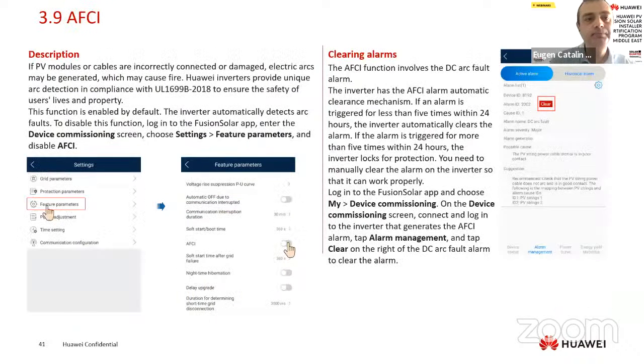The AFCI function. What is this? This is arc fault detection. When the PV module or cable is incorrectly connected or damaged, an electric arc may be generated. What we need to know about this function is that it comes enabled by default on the inverter. And if you have a fault and the alarm is generated more than 5 times in 24 hours, the inverter will not clear the alarm automatically.